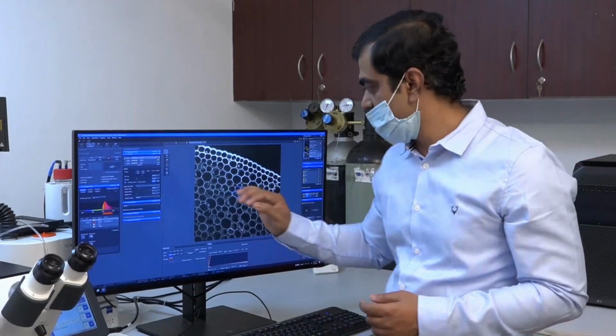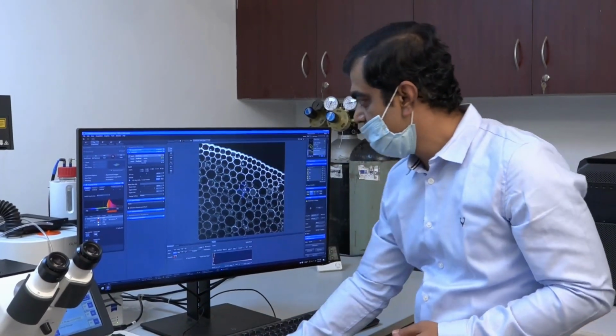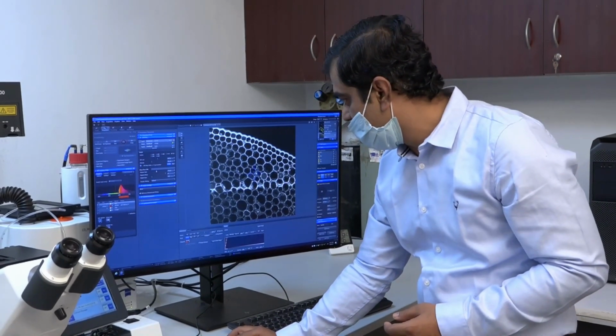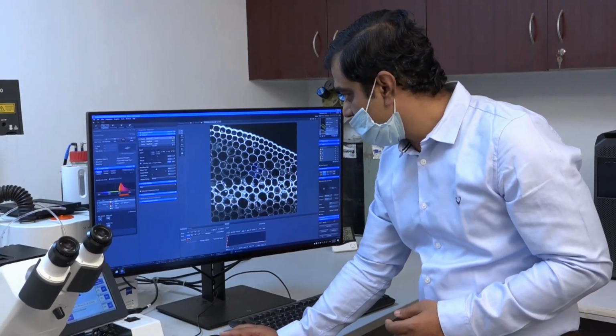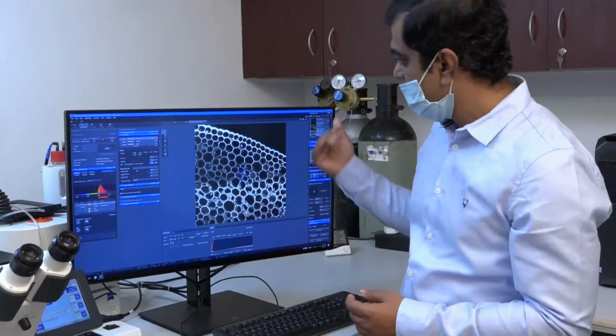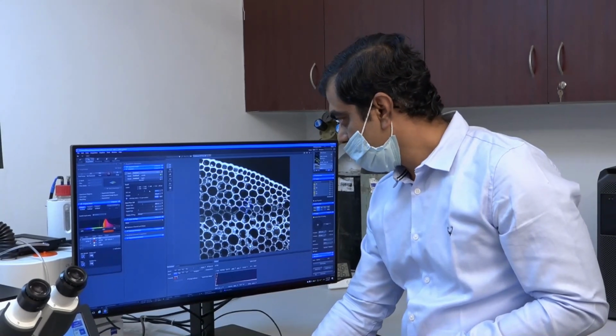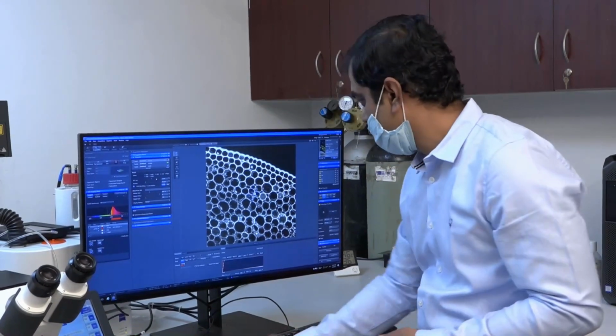But the red dots are not available, you cannot see them here. So we can still take the liberty of increasing the detector voltage slightly so as to improve the signal to noise ratio to a certain extent, better than the previous one.